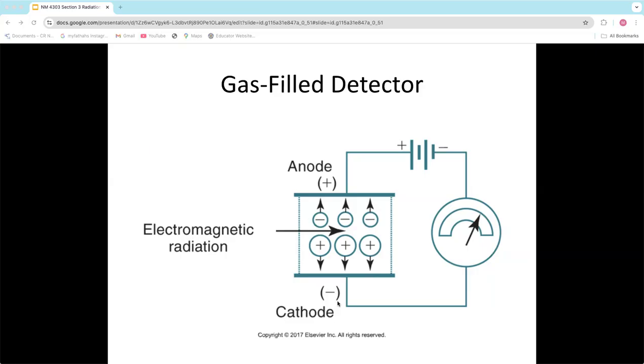Now, that separation happens because you have a voltage across the line, right? So you have a voltage that pulls those apart. Very similar to in the X-ray tube where you have some thermionic emission, you apply voltage and it goes across and creates our X-rays, right? So this is the same idea. It's pulling those two things in separate directions once that reaction happens. And so that's kind of your basic principle. And the idea is that the more gamma rays that it sees coming in, and the more ionization occurs, the more that those separate. And so what happens on your meter then when the voltage is applied is you get some kind of reading on your meter, okay? So the more that it sees, the more ion pairs are created and the more read you're going to get on your meter, okay? And that's kind of the basic thing that happens.